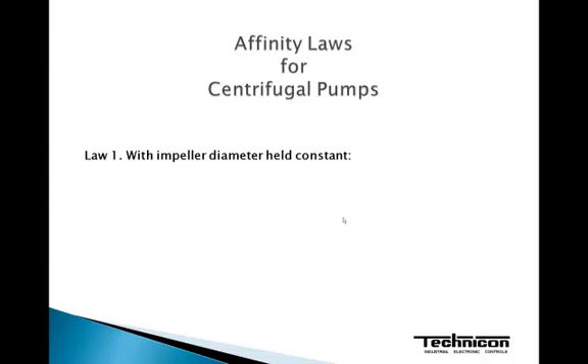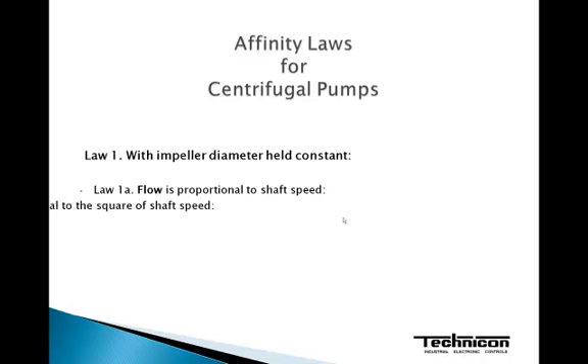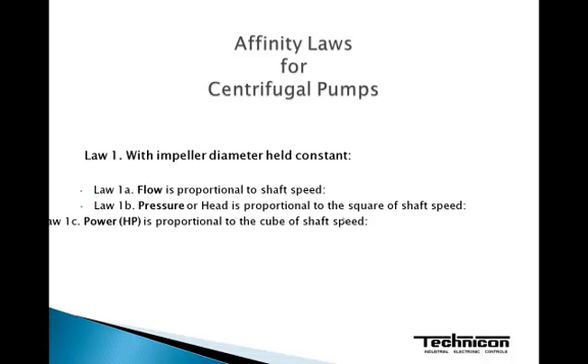The affinity laws for centrifugal pumps tell us that if we have an impeller that is a constant diameter, first of all, the flow is proportional to the shaft speed. The pressure or head is proportional to the square of the shaft speed. And the horsepower or power is proportional to the cube of the shaft speed.